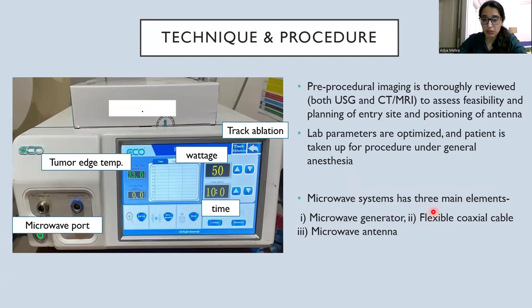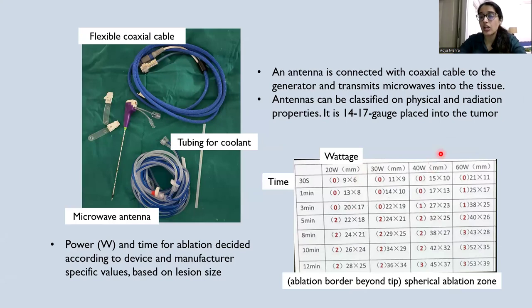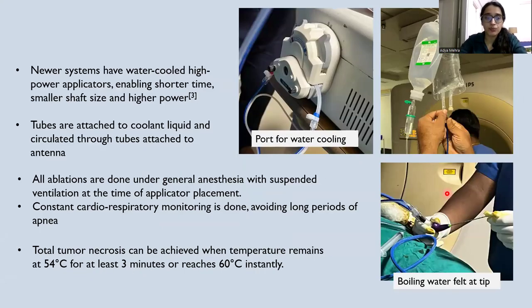Microwave systems have three main elements: the microwave generator with wattage and time display, option for tract ablation, and display of tumor edge temperature. The microwave antenna is connected via coaxial cable to the generator and transfers microwaves into the tissue. These antennas are based on physical and radiation properties and are usually 14 to 17 gauge in size. Power and time for ablation is decided according to device and manufacturer-specific values based on lesion size. Newer microwave systems have water-cooled high-power applicators enabling higher power delivery in a shorter time.